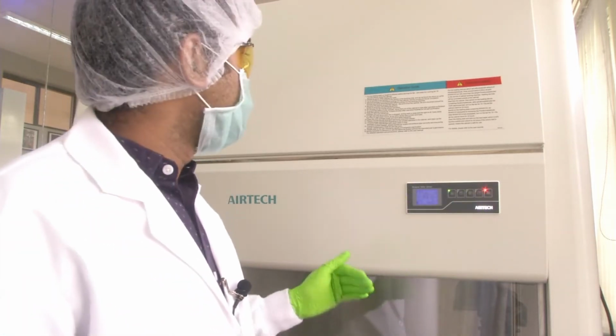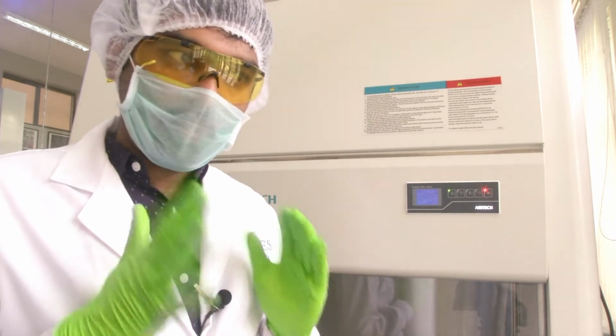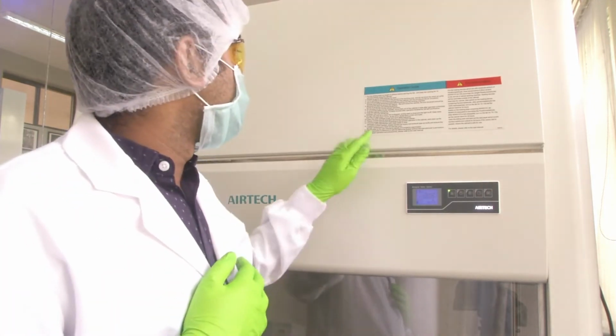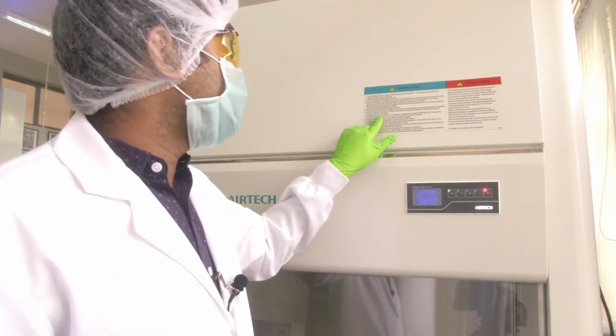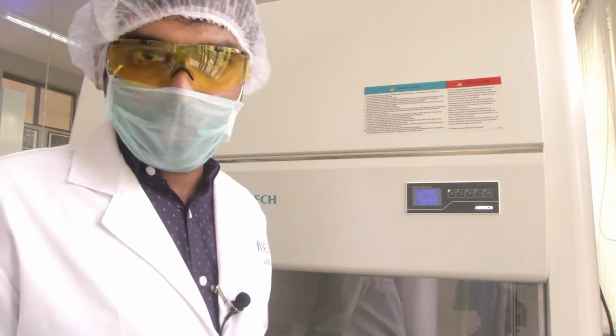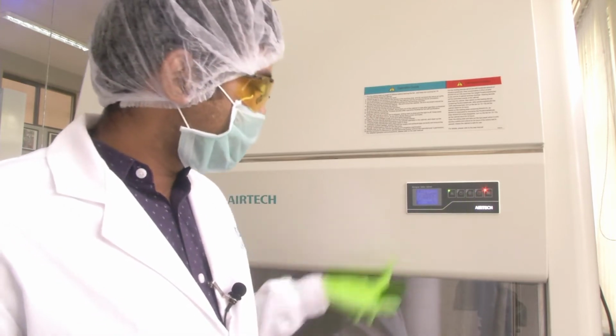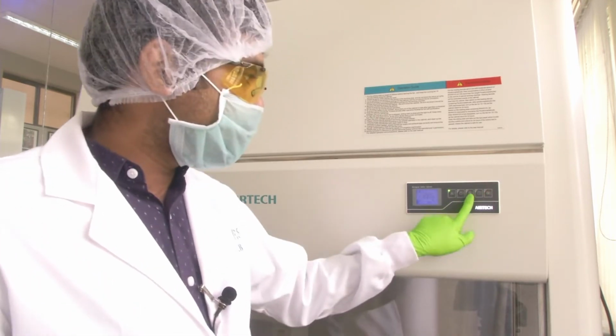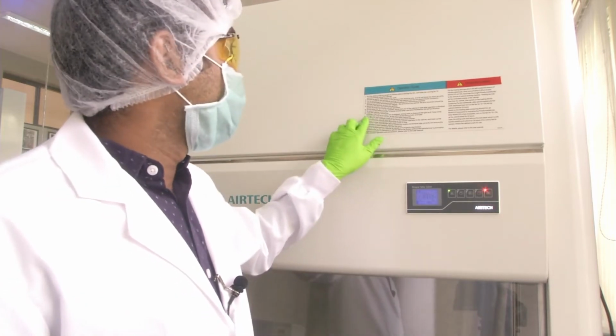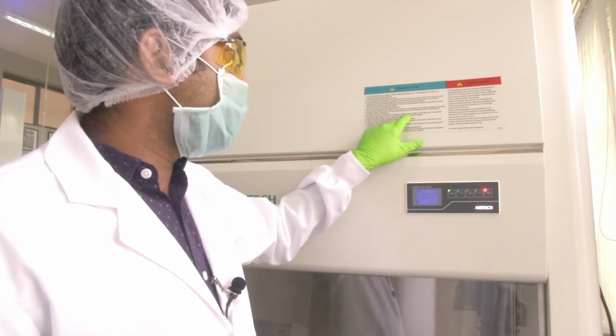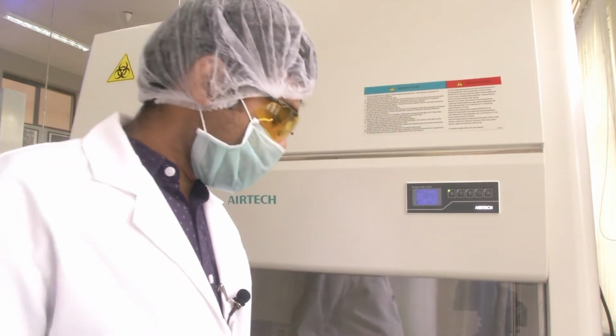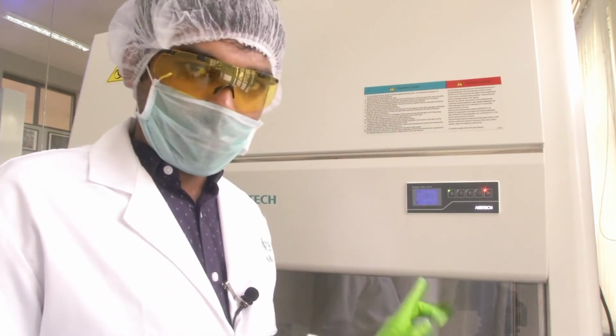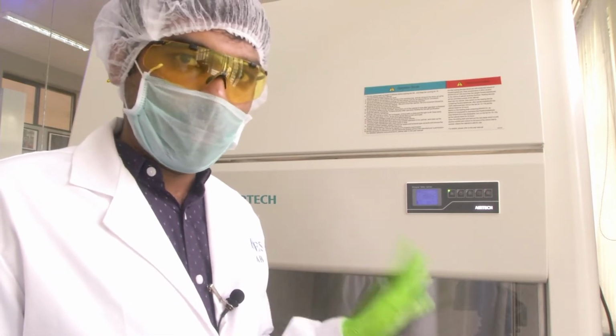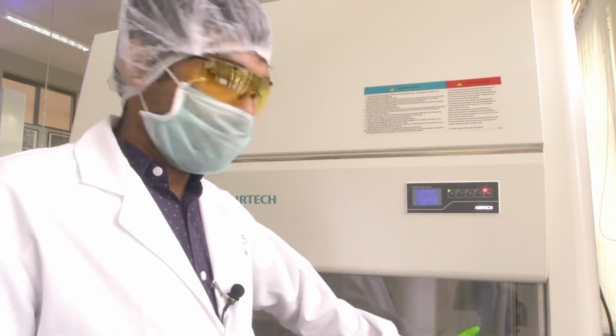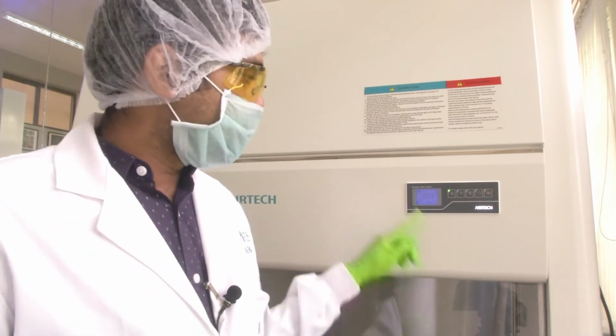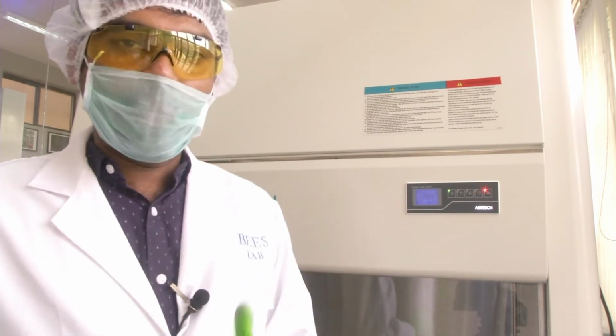Now I have muted it, because for 15 minutes the siren will run, because it is telling us that it is purifying. Then UV light can only be on when the fan is stopped. We have seen it. If I try to switch on the UV light when the fan is on, it will not switch on. See, I am trying to switch on, it will not switch on. UV light can only be on when the fan is stopped, the sliding sash is closed and the light is off. When all these situations are satisfied, only then can the UV light be switched on. The sliding sash should be closed and the fan should be off, then only the UV light can be switched on.